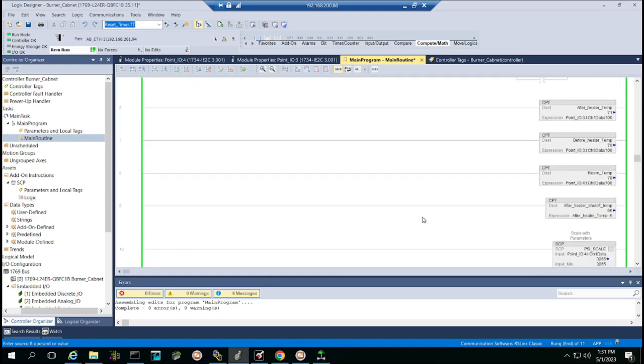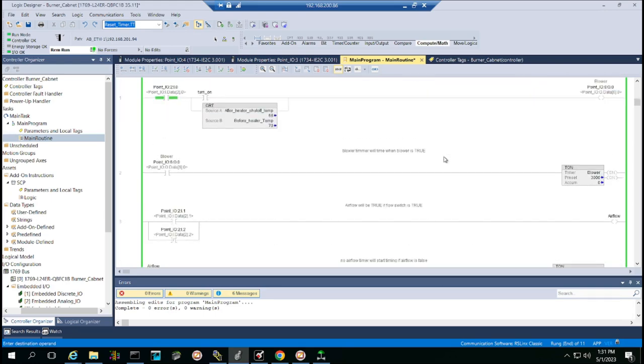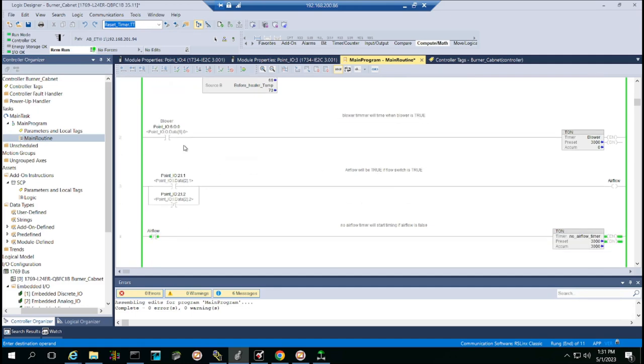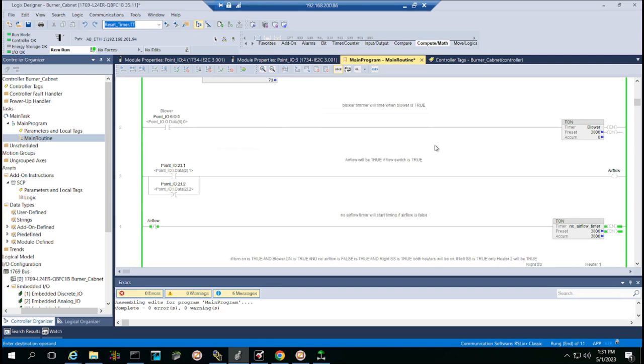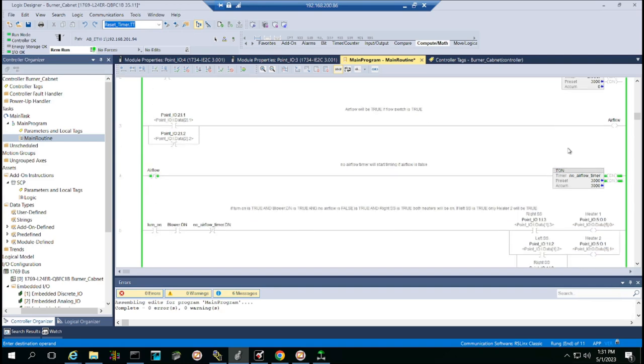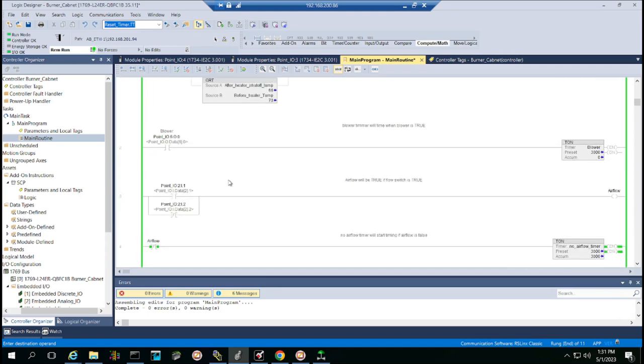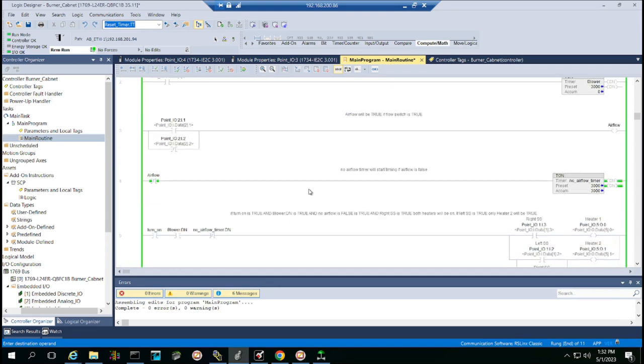And I also have a compute instruction down here just to subtract that after heat temp by 5, just so it doesn't have to be exact, but as long as it's within 5 degrees, the blower will shut off. So then I just have a little on delay timer. When the blower turns on, I let it blow for 3 seconds before it can turn on any heaters. That's just basically making sure we have airflow. And so this right here is an airflow switch, and it comes with a normally open and normally closed set of contacts just for redundancy. So if both of those are, one's false, one's true, this airflow bit will be true.